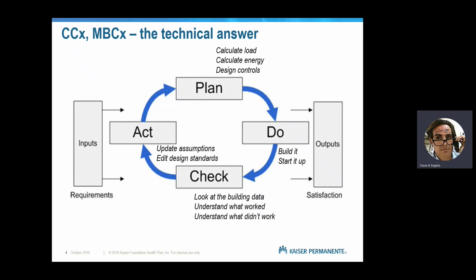And it's going to be a process. I'm not going to lie. If you're a design engineer, the first time you use a connected commissioning system to validate a building, it is going to hurt. And I mean, it actually hurts. Egos are shattered and just left in pieces on the floor. And the second and the third times that you use a connected commissioning system to validate a building, it still hurts. It still hurts badly. But if we do this regularly, day after day, building after building, it gets better. We learn, assumptions can get updated, and things get better little by little. One building is not going to do it, but generation after generation of designs, we can absolutely move towards accuracy.